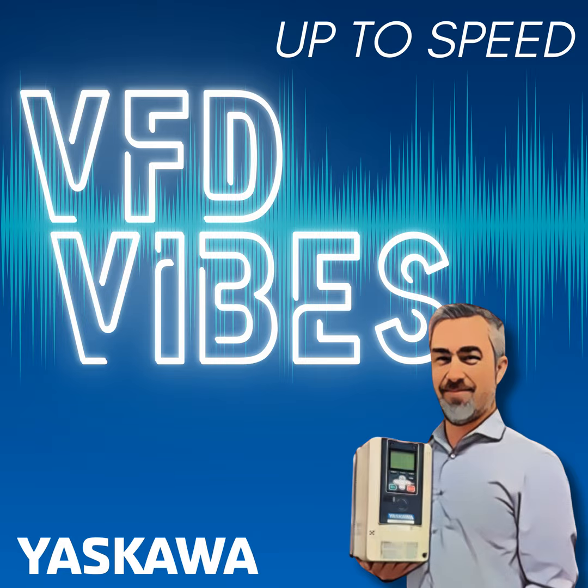Now, let me say this. That was one instance out of like thousands of installations that have drives. Most of the time, you put an EMI filter in there and it does exactly what it's supposed to do, right? Yes. It helps out with the EMI. And the unfortunate aspect of my job and of people in tech support is people don't call tech support and they don't call applications when everything's working correctly. The only time we get a call is when things are not working the way they're supposed to.